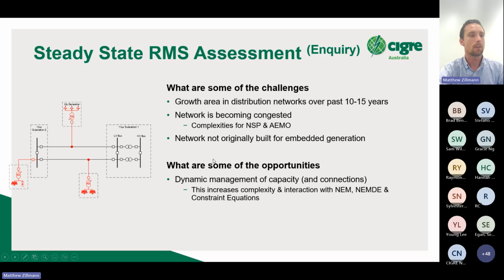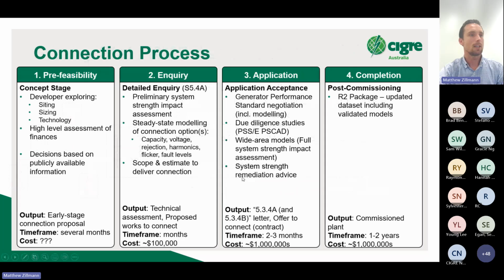What are some of the opportunities? Definitely dynamic management of capacity. This has historically been done at the transmission level and at the NEM level. AEMO manages the market, both the financials and the bidding process, but also dispatch via their NEM dispatch engine, NEMDE. That manages not just the financial side, but also how we apportion dispatch capacity if multiple generators bidding into an area result in a network constraint, ensuring there's no thermal constraint or exceeding plant ratings. That hasn't usually happened at a distribution level, because there haven't been as many generators, and it's always been a bit further down the network than has necessarily been valuable. But that's now changing.